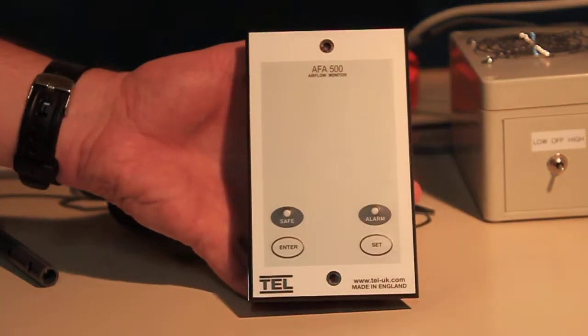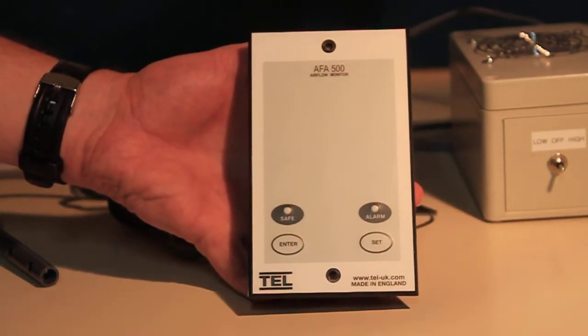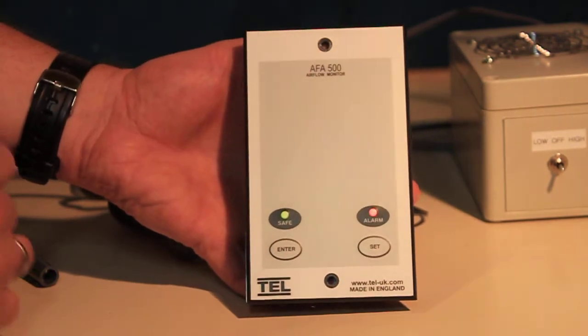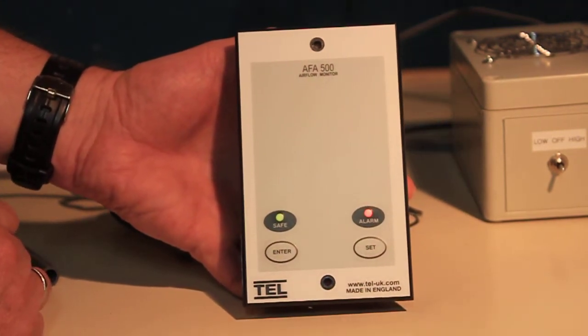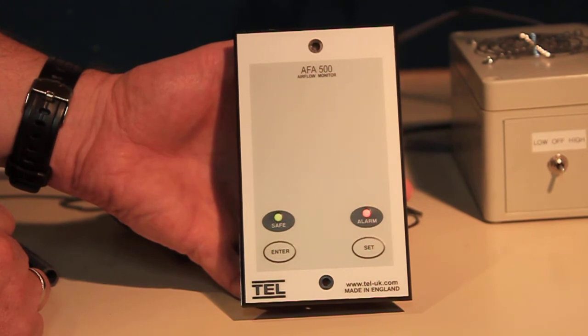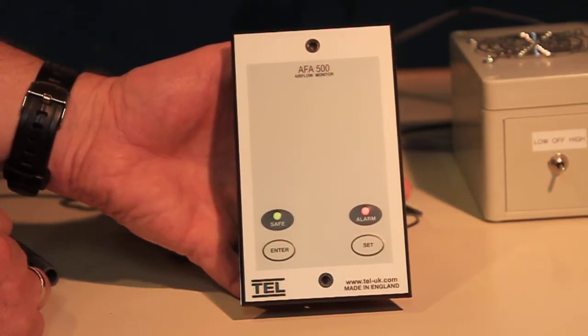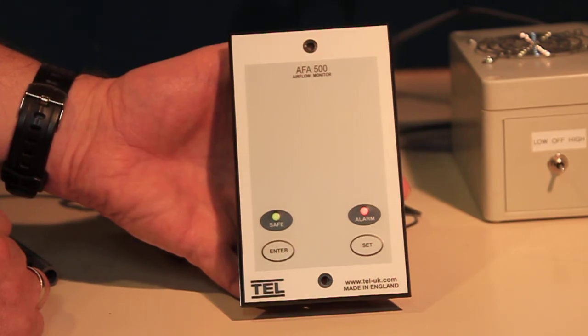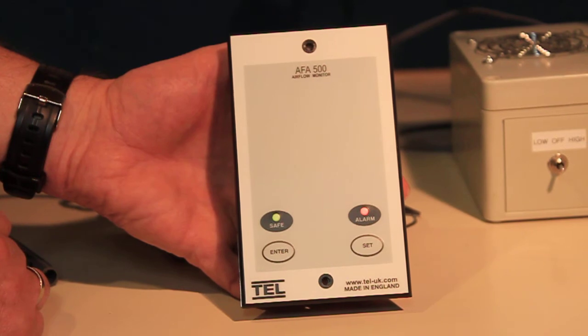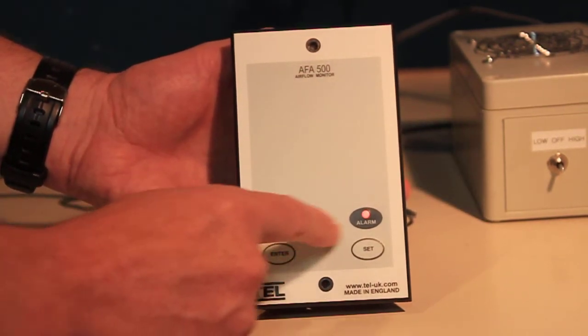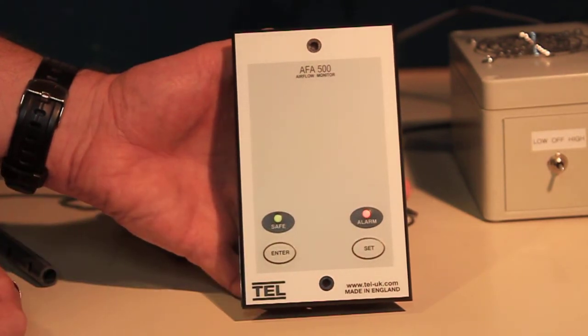When the unit is powered up, the following sequence of events occurs. First, the alarm performs a self-test of its functions, LEDs, and audible alarm, approximately 2 seconds, and then initiates a delay timer of 30 seconds to allow the airflow sensor to stabilize. During the 30-second stabilizing period, all alarms and relay outputs are deactivated and the red and green LEDs remain on. This demonstration unit allows us to simulate airflow.